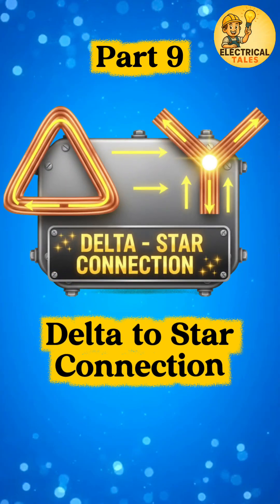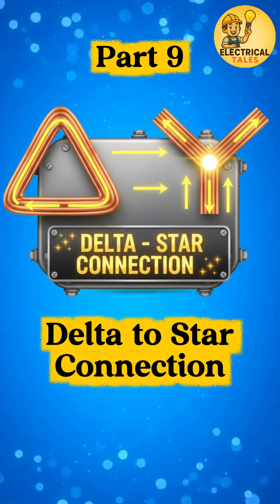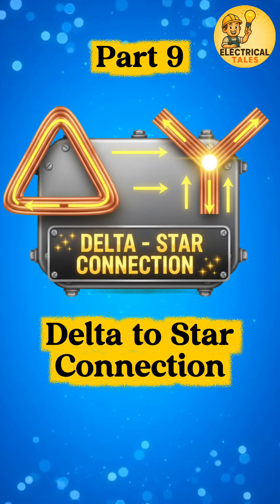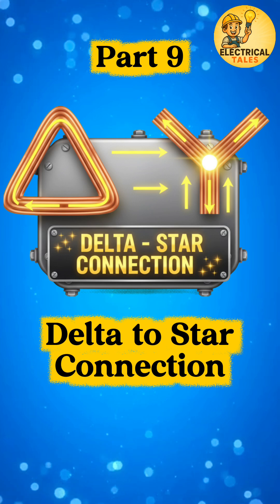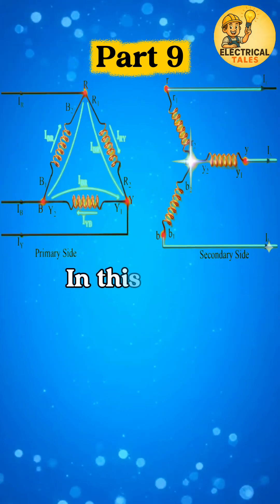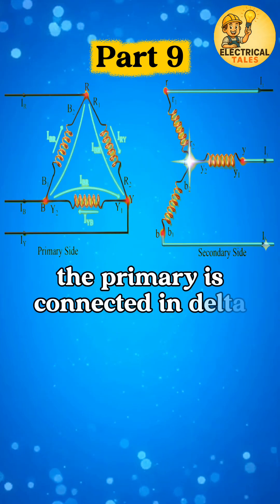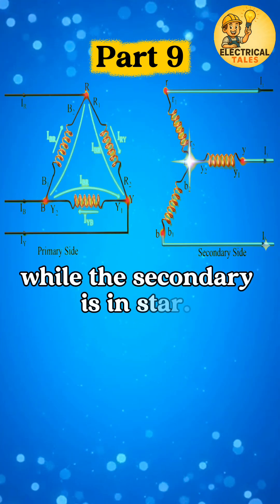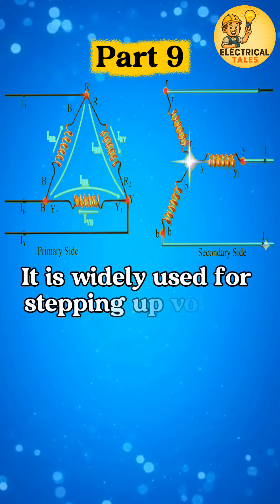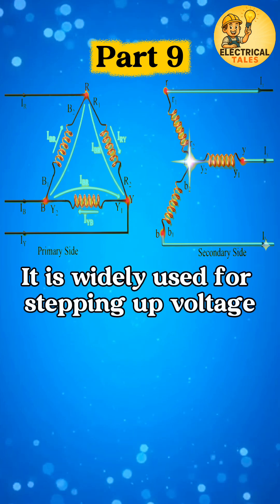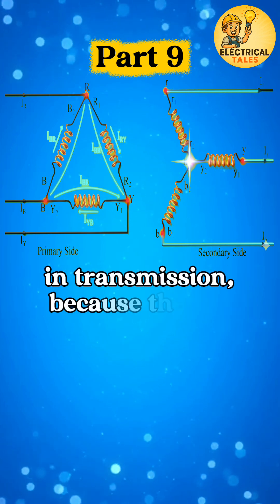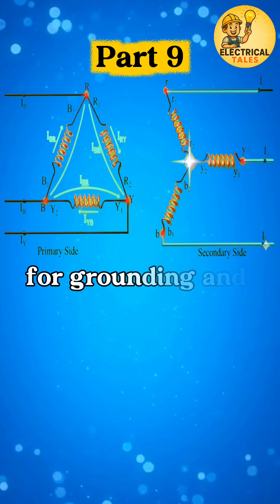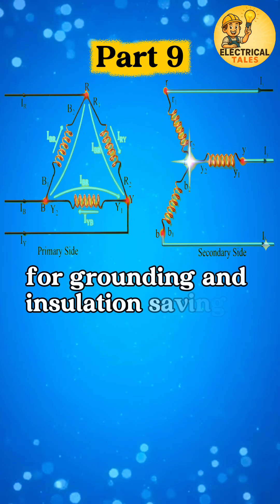After star to delta, let's now uncover the reverse arrangement: the delta to star transformer connection. In this type, the primary is connected in delta while the secondary is in star. It is widely used for stepping up voltage in transmission, because the star side provides a neutral point for grounding and insulation savings.